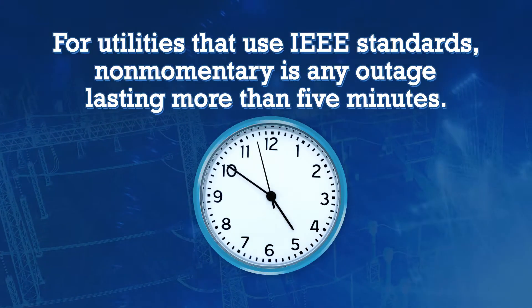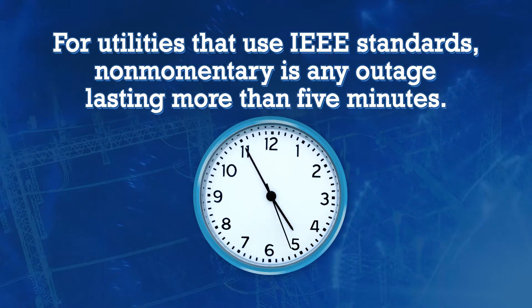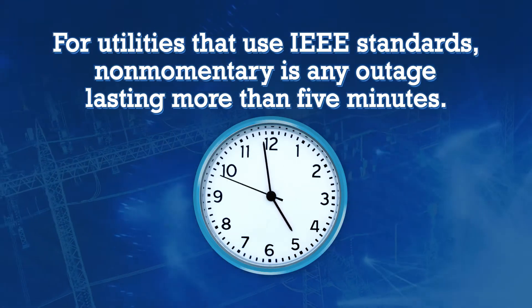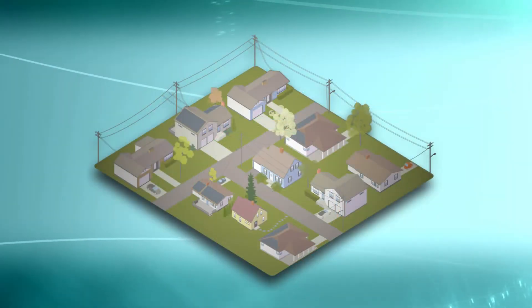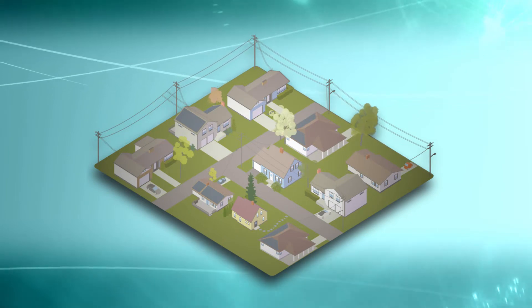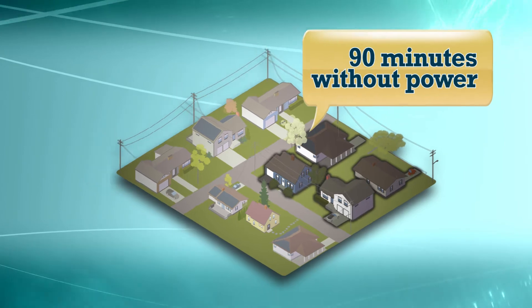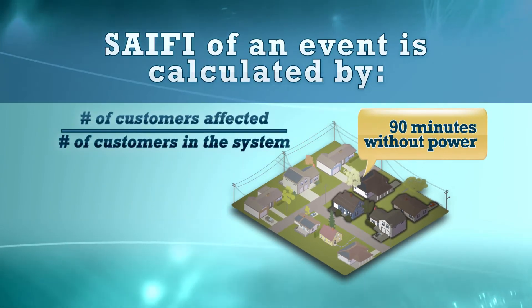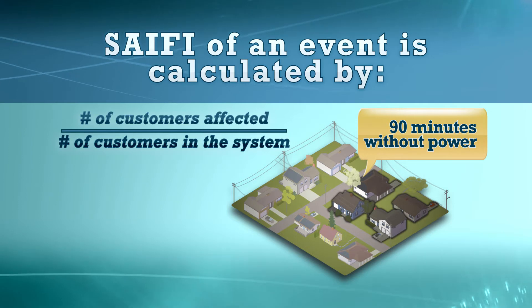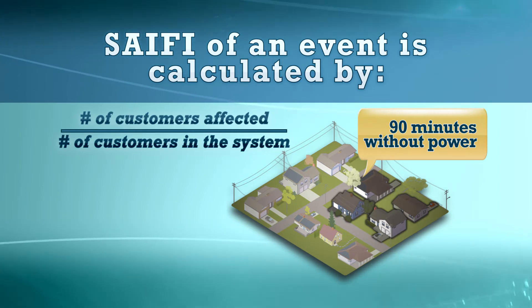The SAIFI and SAIDI collected are yearly summed values of all non-momentary outages. For utilities that use IEEE standards, non-momentary is defined by any outage lasting more than five minutes. SAIFI of an event is calculated by the number of customers affected divided by the number of customers in the system, or the percent of customers affected.